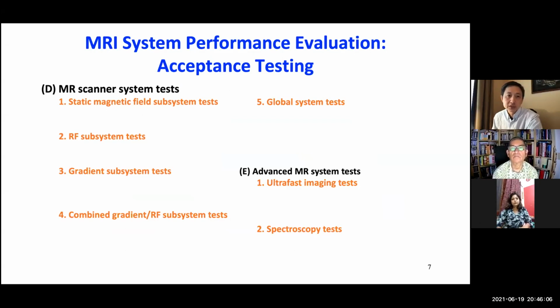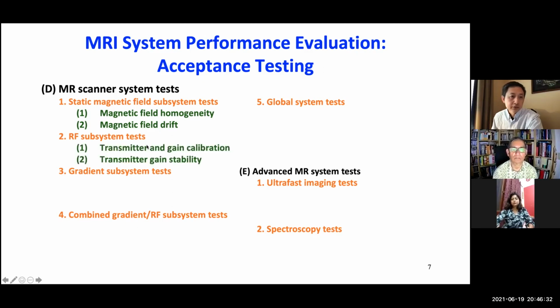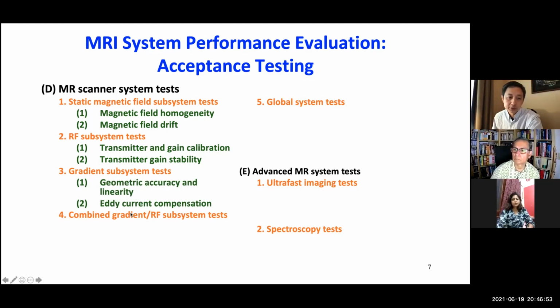So what we do both during acceptance testing and also annually is the scanner testing. Here I already mentioned the major items for scanner testing, those 5 items. Just a little bit more detail for magnetic field: we measure field homogeneity, that's spatial homogeneity, and then the field drift over time. For the RF subsystem, we basically monitor the transmitter gain, calibration, and stability. For the gradient subsystem, we make sure the geometric accuracy and linearity are good because they will be affected by the gradient subsystem. And also eddy current compensation.